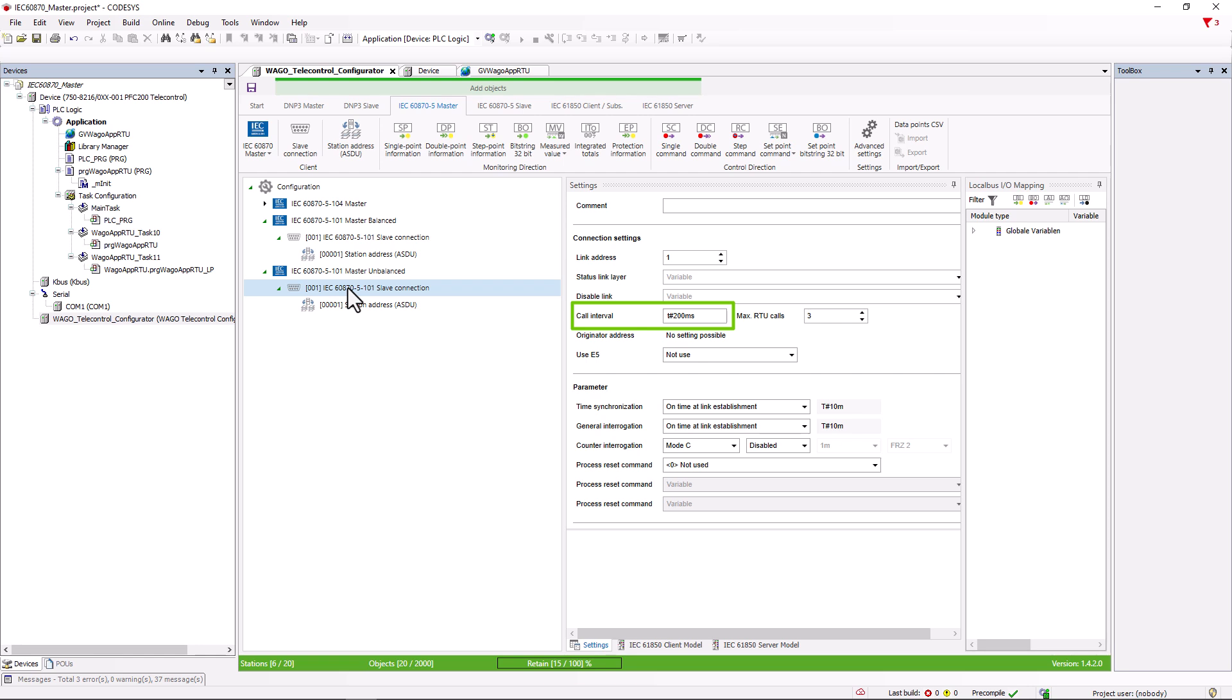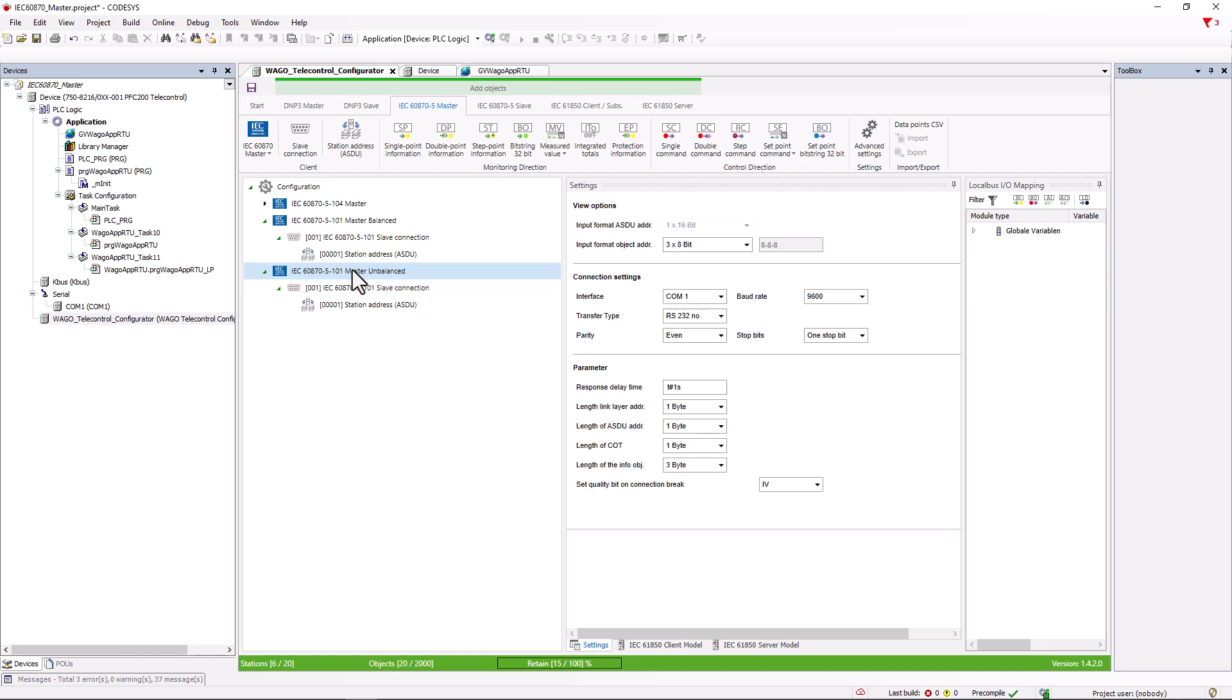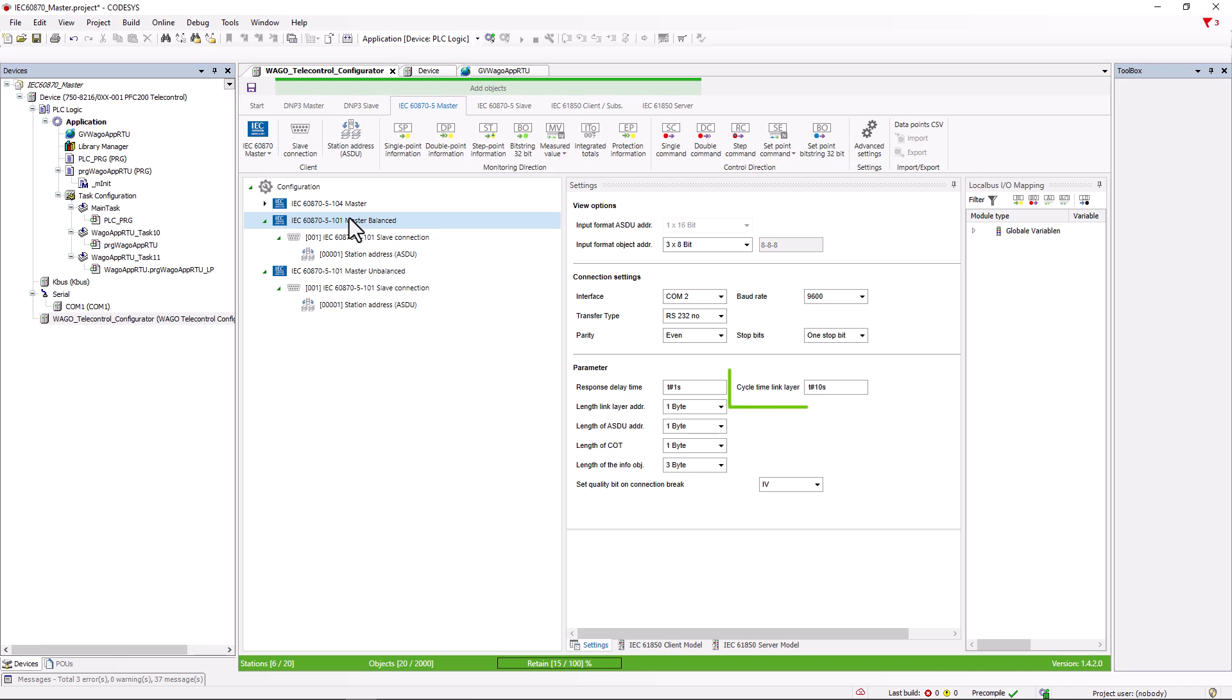However, the polling interval should not be less than 100 milliseconds. Otherwise, collisions may occur in the subsequent process. The General Master settings for unbalanced communication are almost identical to the Balance Master, except of course that the field for the test telegram is omitted, as the communication is constantly checked by polling.